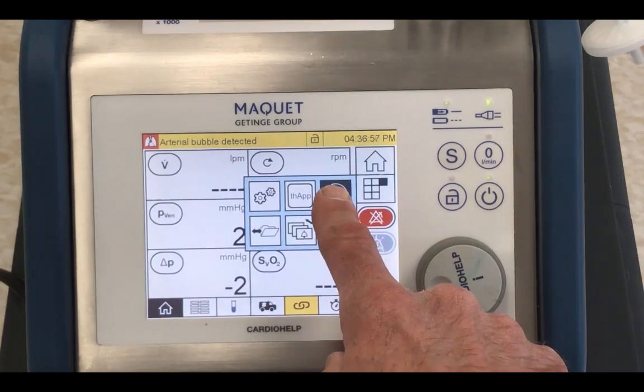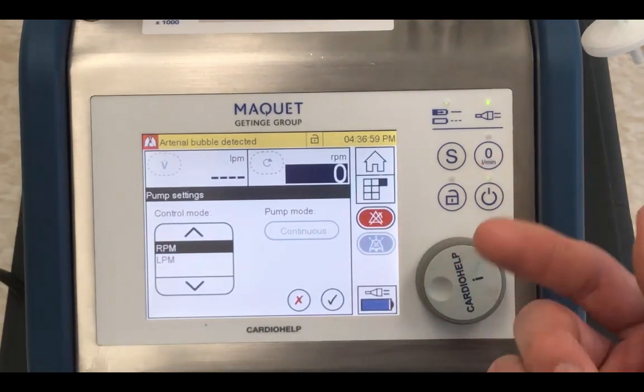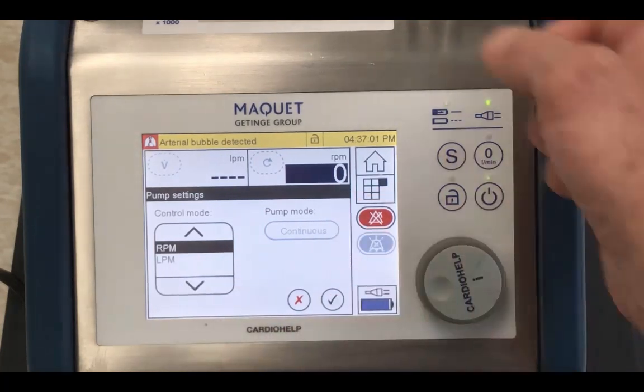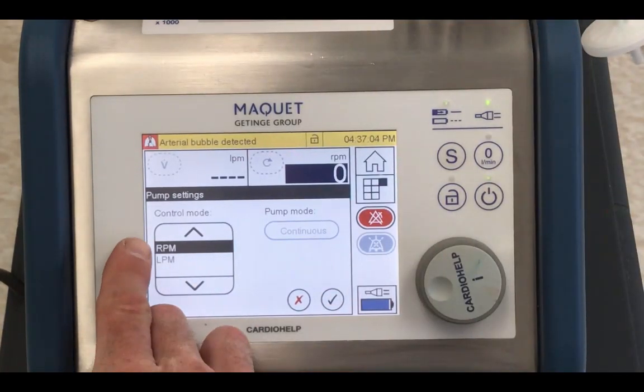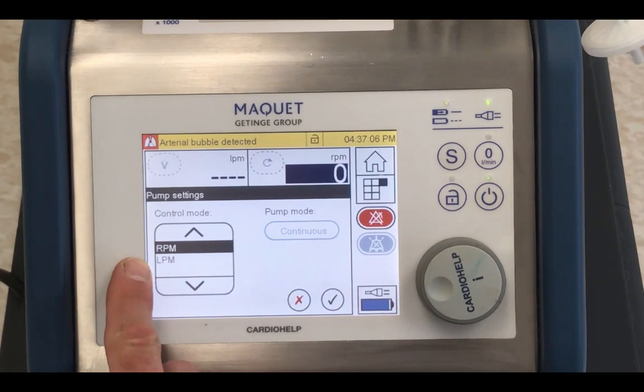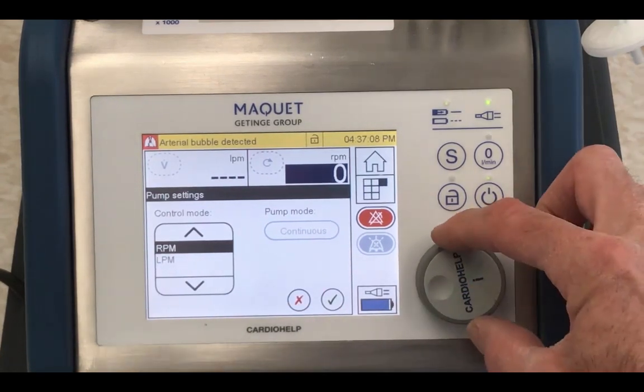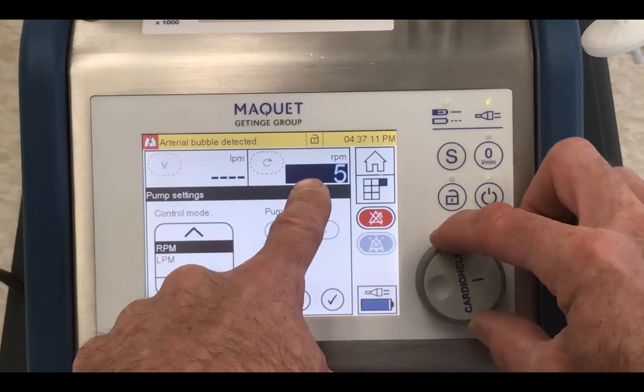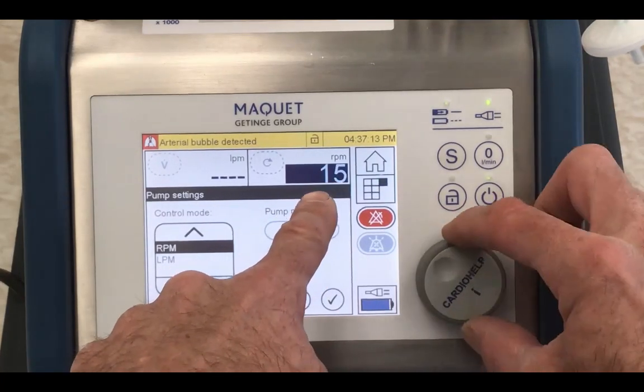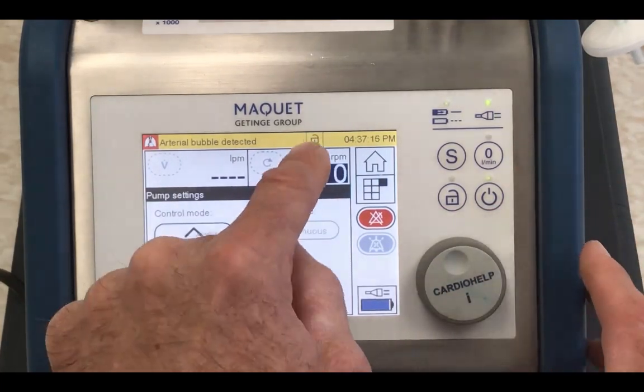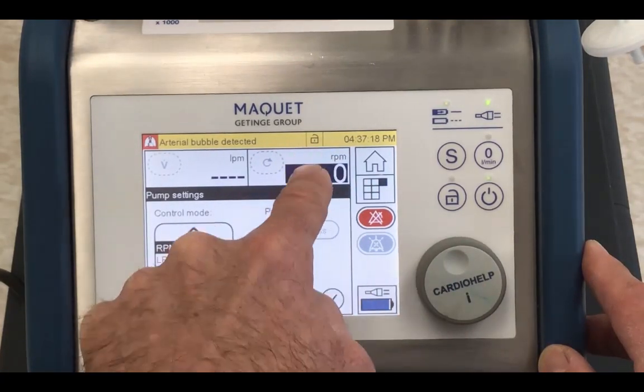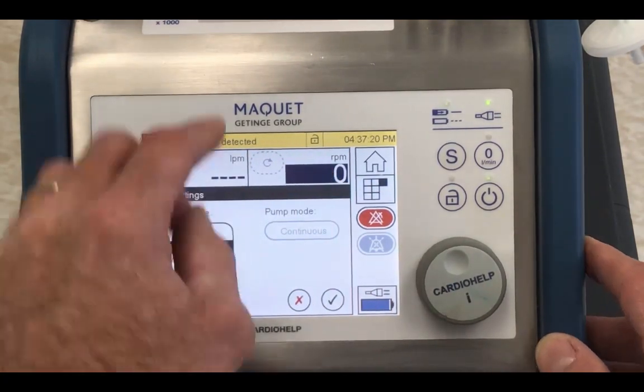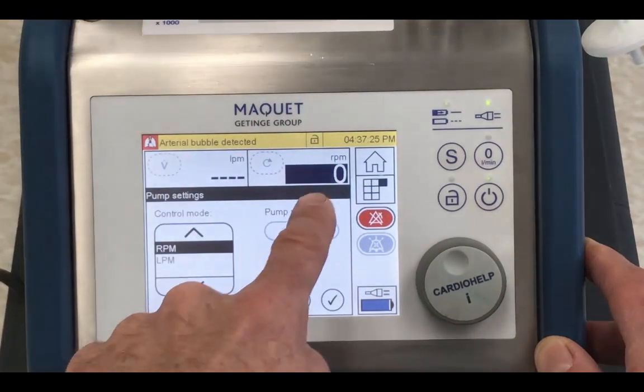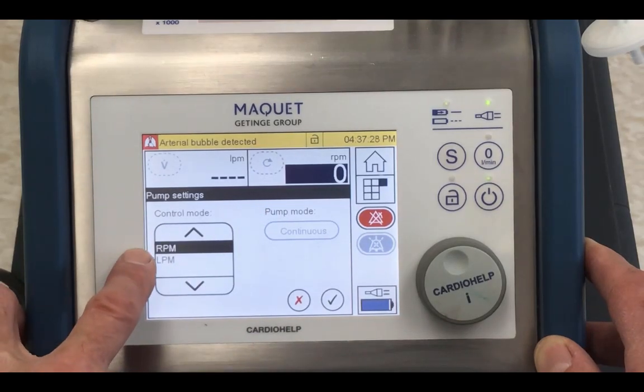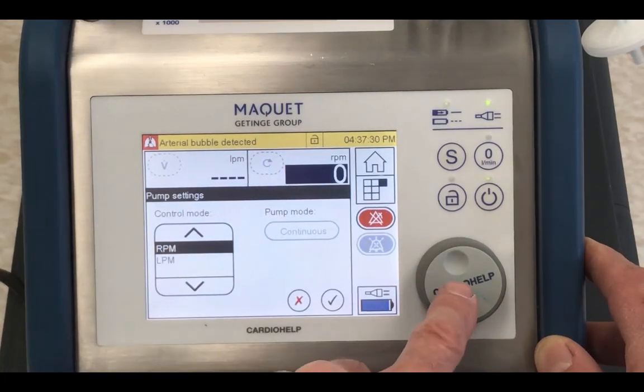This one is about your pump flow. It's an icon of a centrifugal pump, and you can put this system here into RPM mode or LPM mode. In RPM mode, this knob controls RPMs, and you turn it to an RPM. When you release it, that's what you have set. You've set an RPM. And the flow, because these pumps are preload and afterload dependent, the flow will go up and the flow will come down, but the RPMs will not change. If you're in RPM mode, the RPMs stay to what you set.